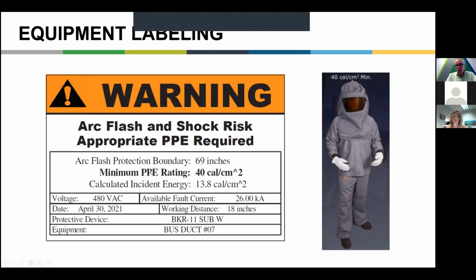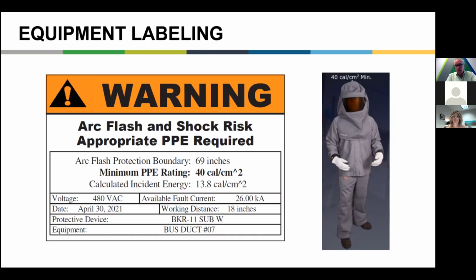For example, let's look at this label just briefly. Arc flash protection boundary, 69 inches. That's the 1.2 calorie threshold, and I don't want to get buried in too much detail here, but I thought we should mention that at least. The arc flash protection boundary is where there exists 1.2 calories, enough to cause a second-degree burn on human skin. So 70 inches away from those live parts, if an arc flash event were to occur, it would be potentially a second-degree burn. Well, of course, you're not going to be 70 inches away from live parts. If you open an access cover or door and you're working in live parts with these calorie levels, you need a suit on.